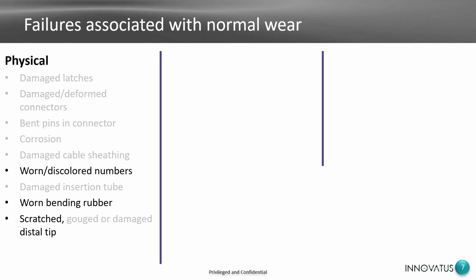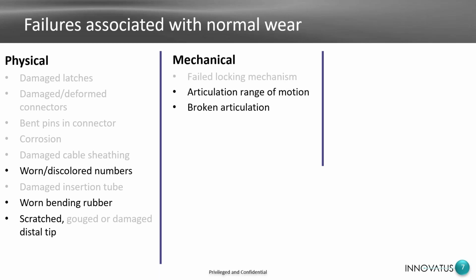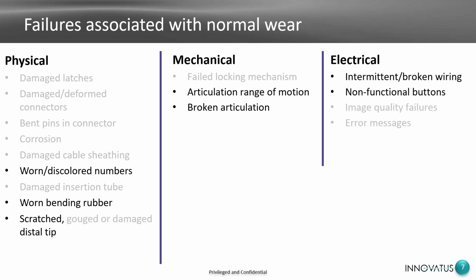So things that are associated with normal wear and tear can be worn or discolored numbers on the insertion tube, worn bending rubber. That bending rubber at the tip that allows the tip to articulate does get worn over time. And then a scratched, gouged or damaged distal tip. The distal tip is the very end of the probe where the array is located. Under mechanical, articulation can fail, either the range of motion or it can be broken. Articulation on TE probes can be adjusted in a lot of cases. Sometimes it does have to be replaced. Again, this is normal wear and tear. And then electrical, intermittent or broken wiring. Over time, wires break. It's the nature of the beast.